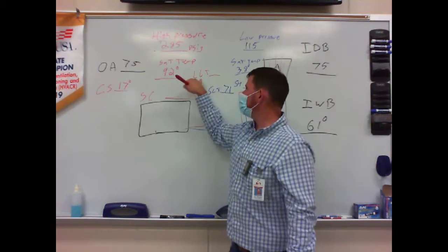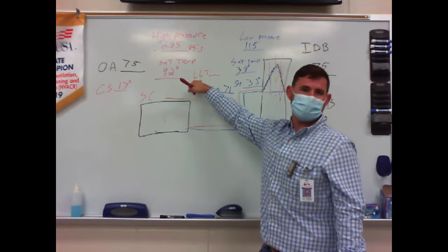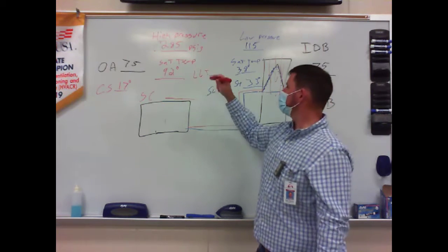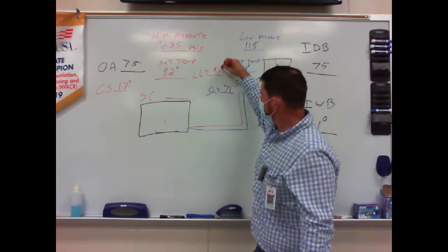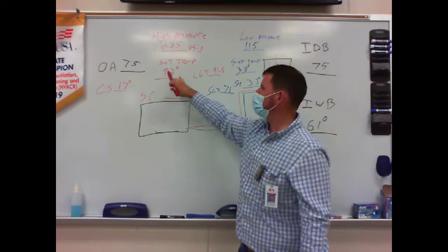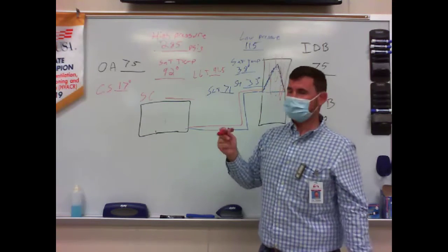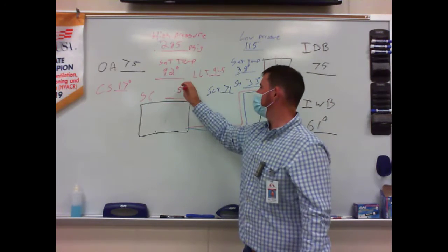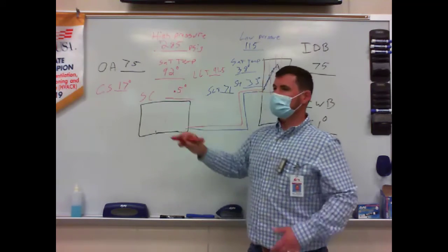What about my liquid line temperature? 91.5. So what was my subcooling? How much did I cool off from my saturation? None, really. So I have no subcooling.